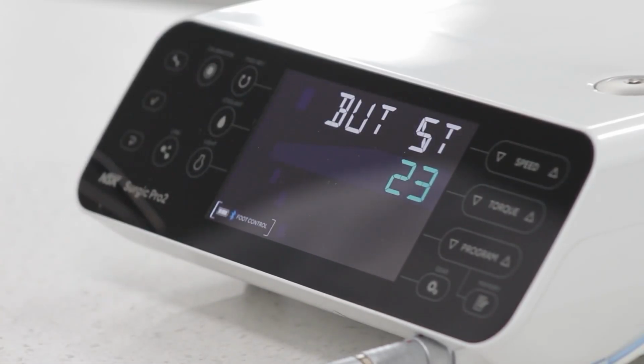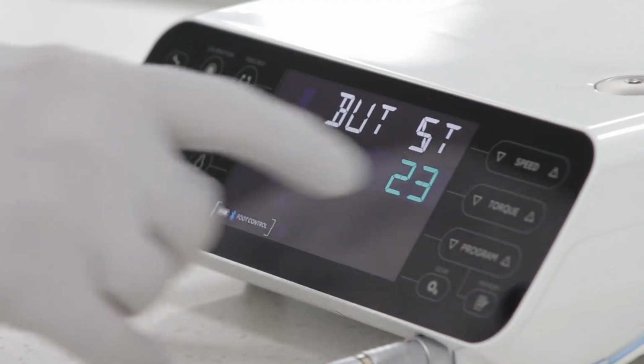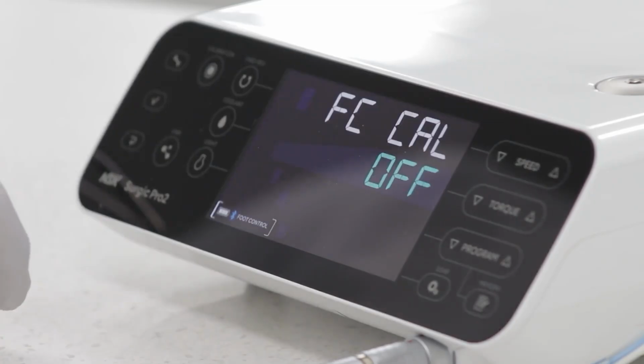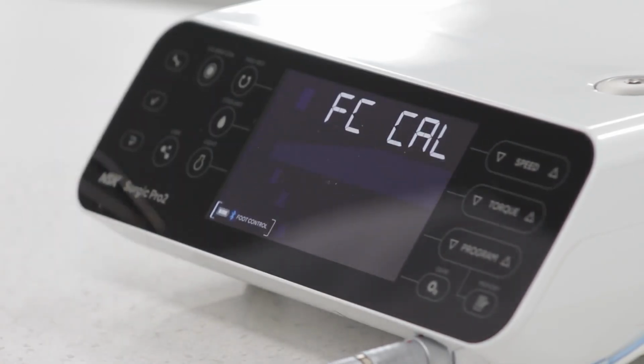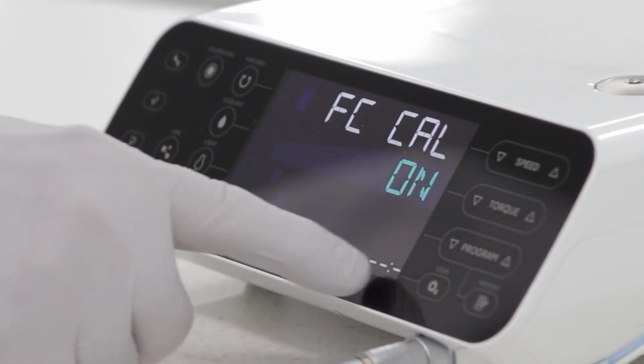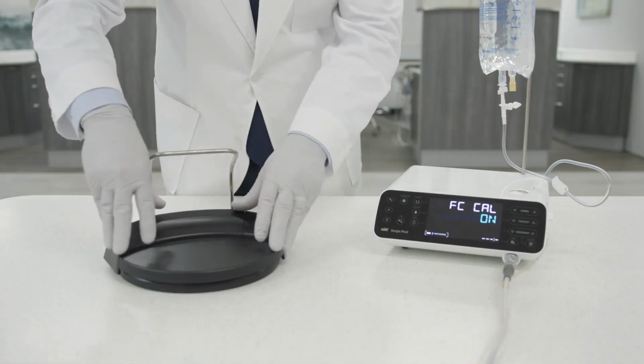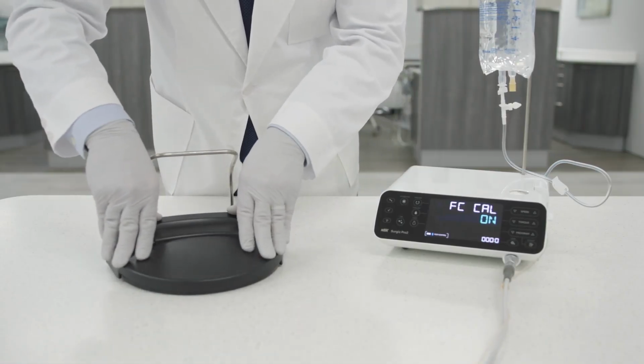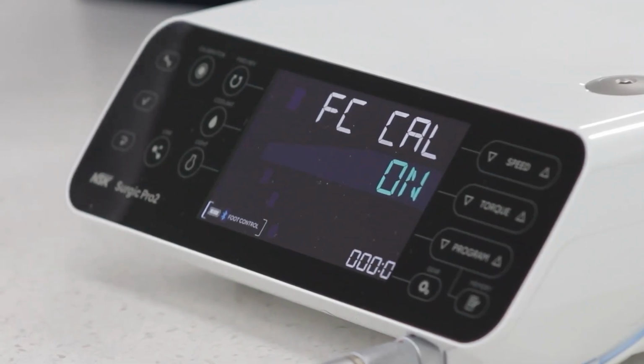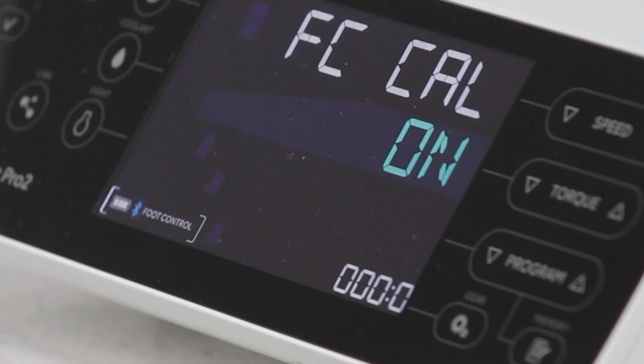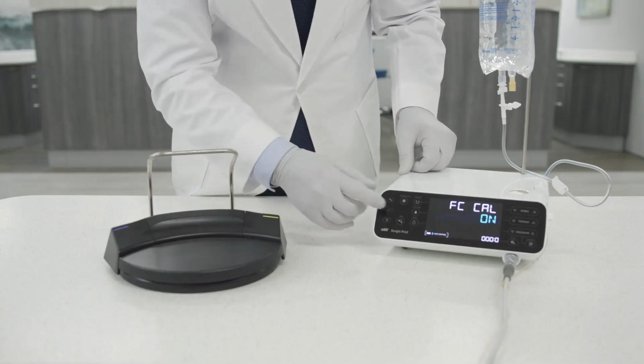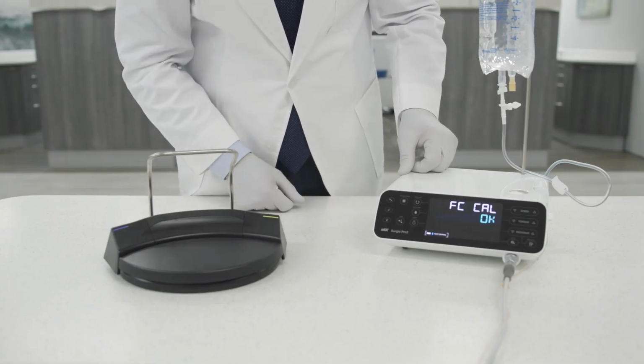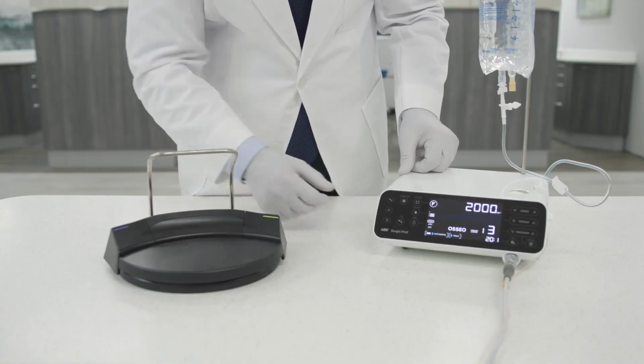Press Enter. Press Speed Up twice to enter FC Cal while Off is blinking. Press Torque Up to change it to On. Then press Enter to confirm that 4 dash lines are displayed on the bottom right corner of the display. These lines represent the buttons and the speed control pedal on the foot control. Fully press all 3 buttons and the speed control pedal. Once 4 zeros are displayed on the screen, foot control calibration is successful. Press Enter. OK will be shown on the display after a beep sound. Press Return twice to return to the main screen.